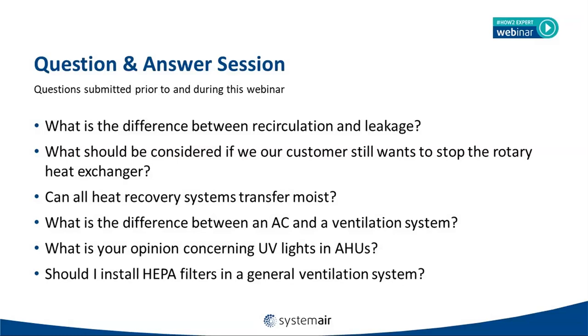Second question we had received prior to the webinar as well: what should be considered if we or our customer still wants to stop the rotary heat exchanger? Richard, I think this is something for you. Yes. You need to consider if your system has sufficient heating and cooling capacity without the energy recovery components. But you also need to consider the startup of the rotor, do regular maintenance and keep cleaning mode active. Thank you, Richard. Here again, focus on correct ventilation. As long as you do it correctly, you're on the right way.